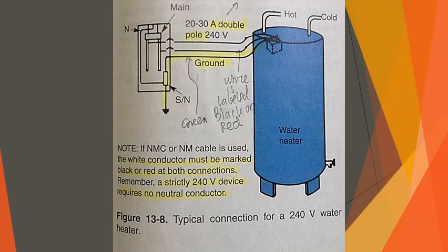Water heaters. A single family home or small commercial enterprise will usually have a 30, 40, or 50 gallon water heater. Electric water heaters require a separate 240 volt circuit. In most instances, the water heater is connected to a 2-pole 20 amp or 30 amp breaker at the main panel or a nearby sub-panel.